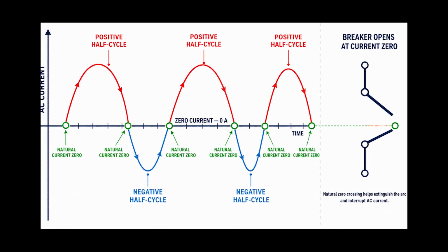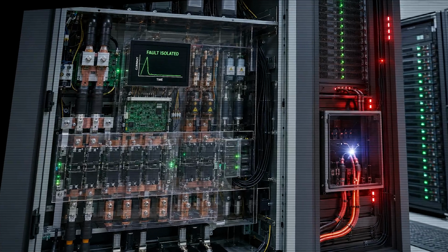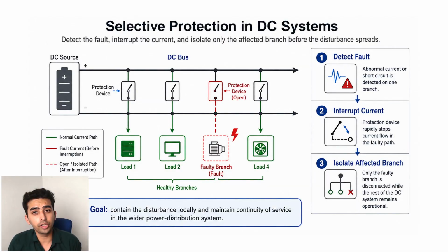Unlike AC distribution systems, in which the AC current crosses through zero at every positive and negative cycle, in DC distribution systems there is no such zero crossing. That's why, if a short circuit occurs, the DC current rises exponentially, and we need a very reliable mechanism to handle short circuit DC currents. The protection systems in DC distribution must detect these faults, interrupt the high DC current, and isolate only the affected branch before the disturbance spreads through the wider DC power distribution system.